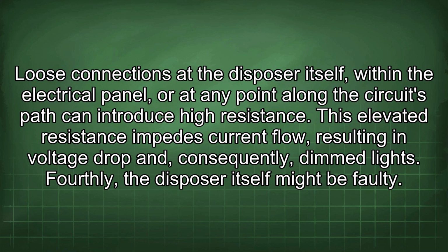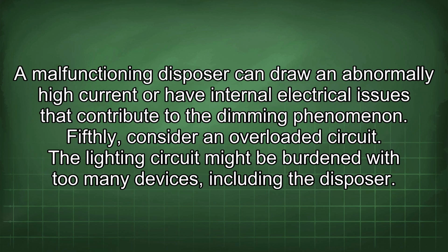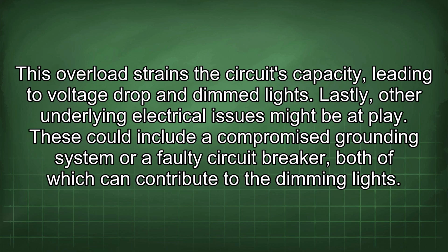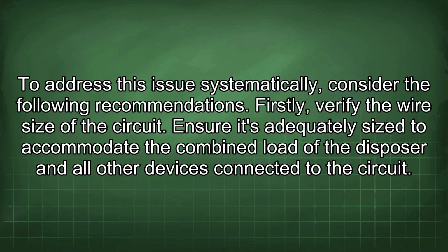Fourthly, the disposer itself might be faulty. A malfunctioning disposer can draw an abnormally high current or have internal electrical issues that contribute to the dimming phenomenon. Fifthly, consider an overloaded circuit. The lighting circuit might be burdened with too many devices, including the disposer. This overload strains the circuit's capacity, leading to voltage drop and dimmed lights. Lastly, other underlying electrical issues might be at play. These could include a compromised grounding system or a faulty circuit breaker, both of which can contribute to the dimming lights. To address this issue systematically, consider the following recommendations.